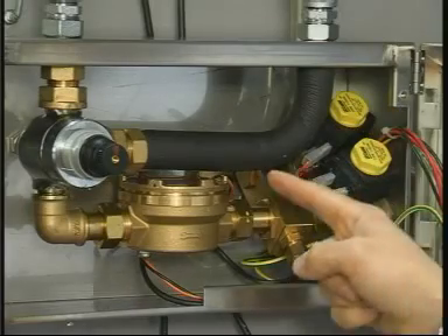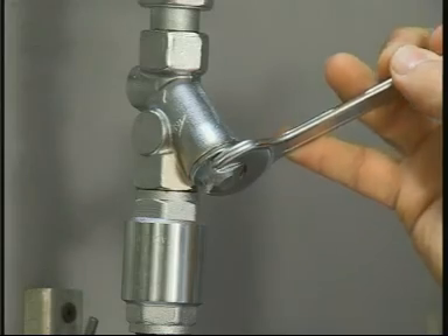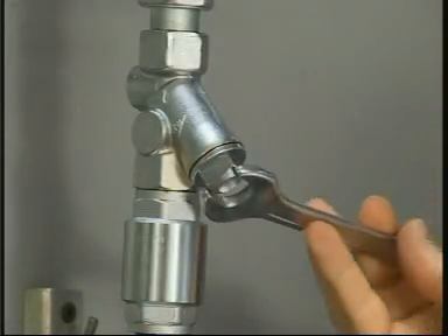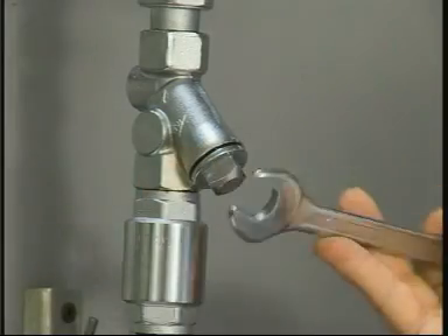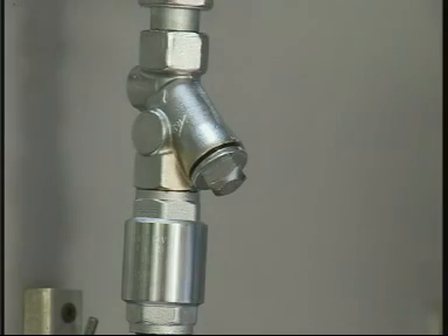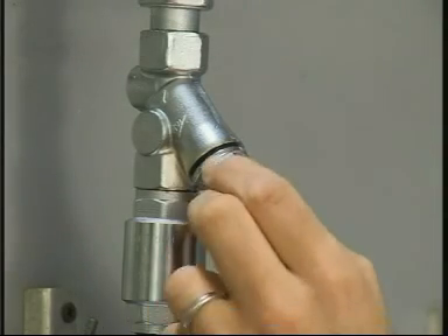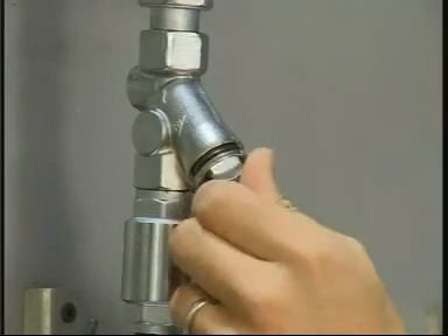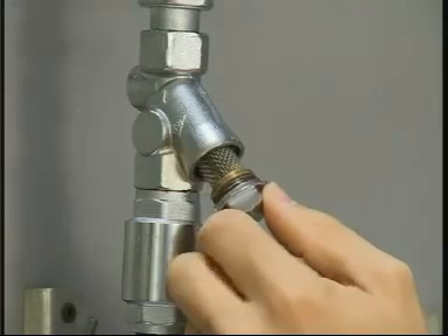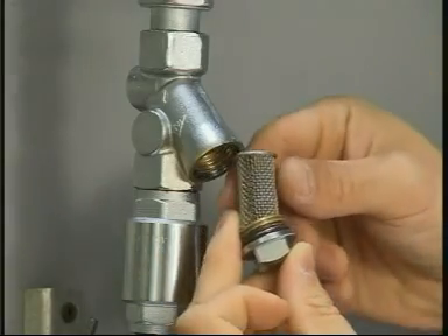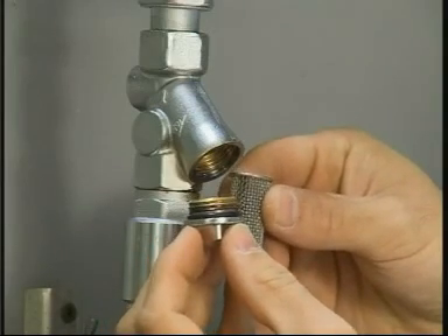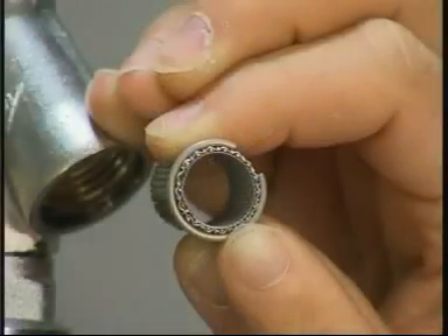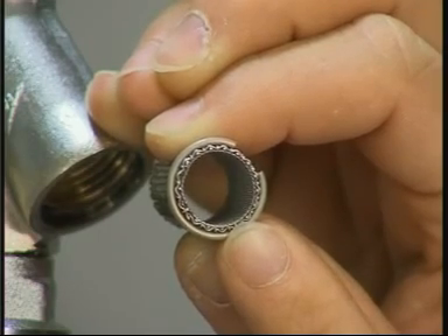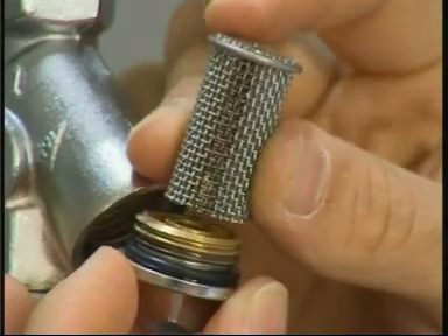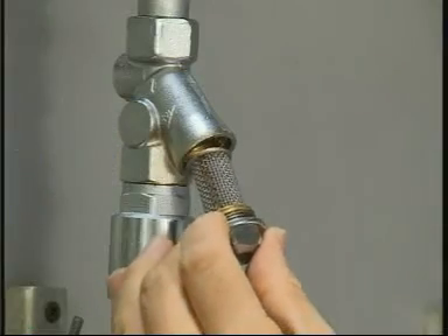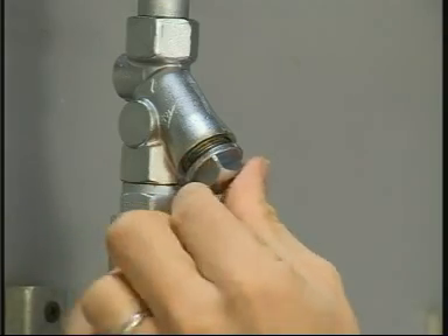To check the filters, or to carry out their cleaning, operate in the following way. Close the inlet ball gate valves and release the pressure. Switch off the supply to the machine. Unscrew with a spanner number 15 the filter cap. Remove the internal stainless steel double mesh filtering element. Clean, if necessary, the indicated zone with water or compressed air. If eventual limestone incrustations are persistent, it is possible to clean the filter with anti-limestone acids for stainless steel. Assemble as shown.